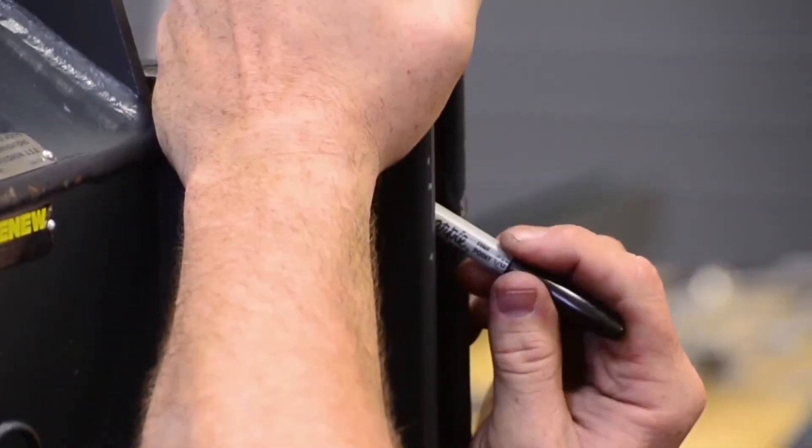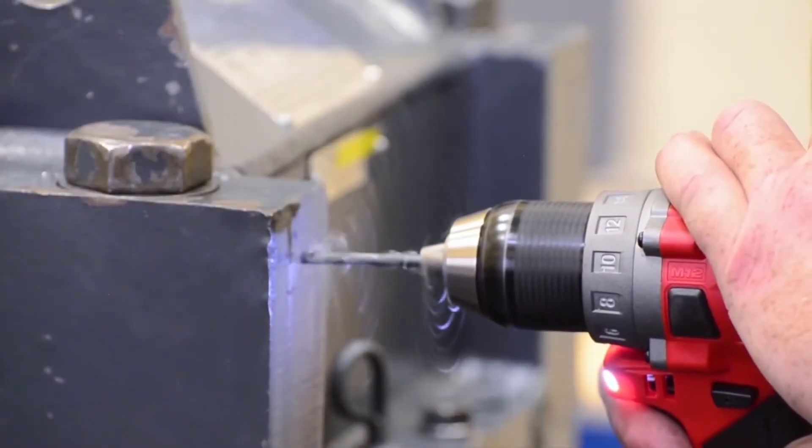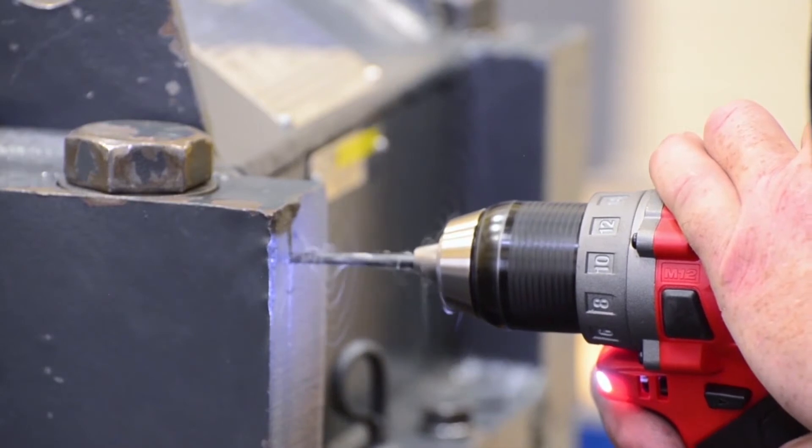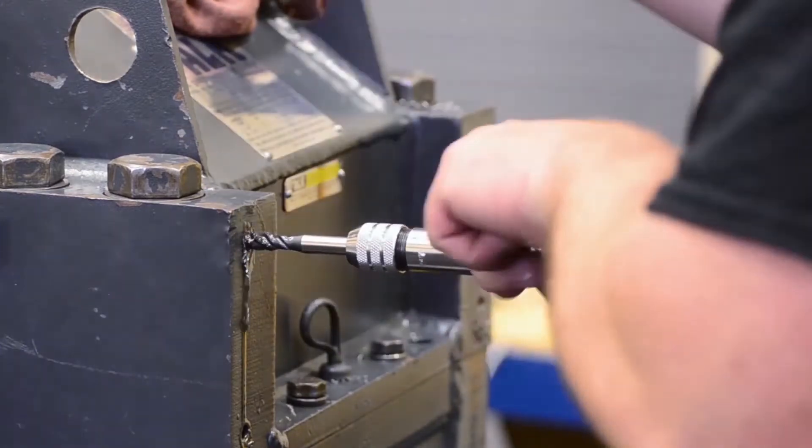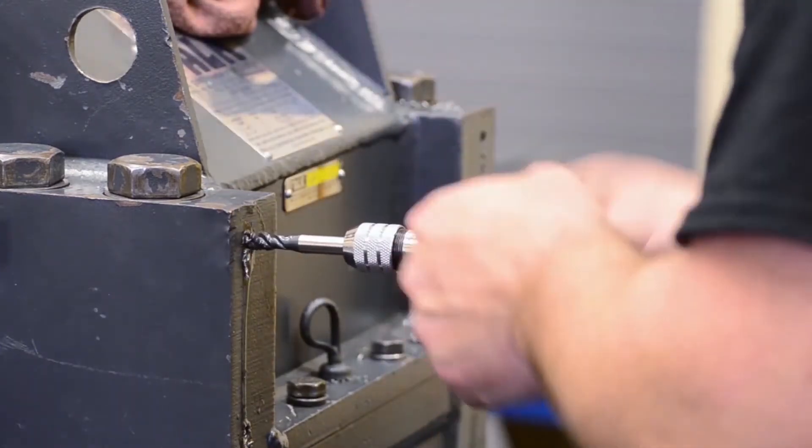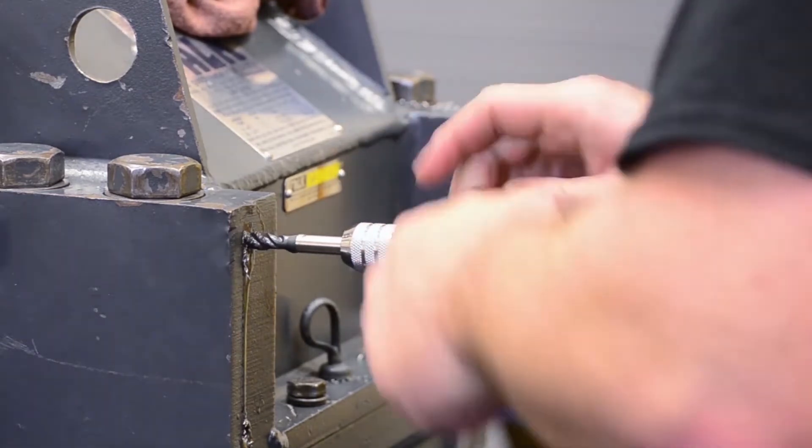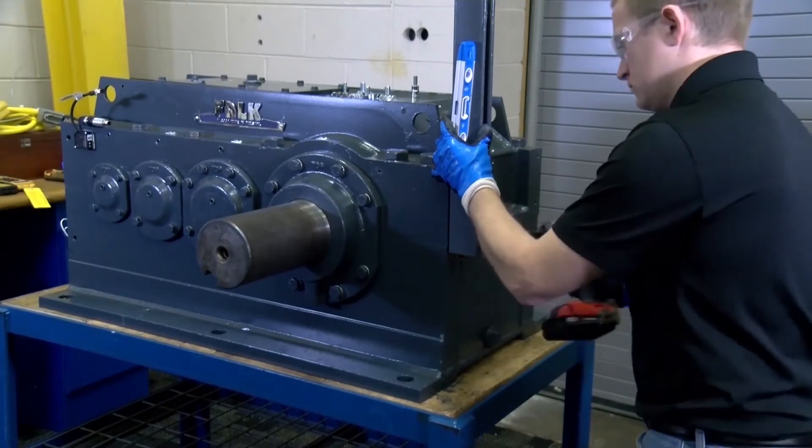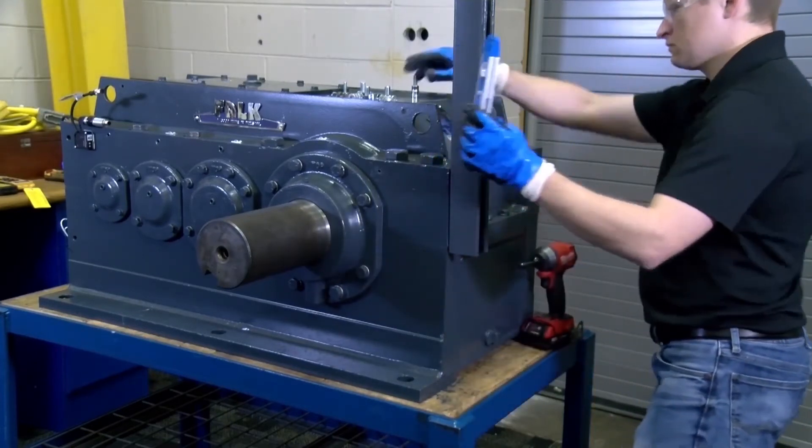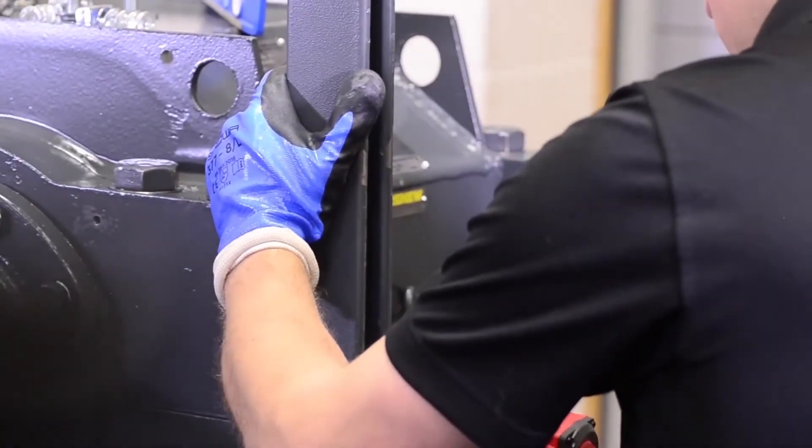Mark the hole locations on the drive and verify the positions align with the holes in the unistrut. Use an F-size drill bit and drill to a maximum depth of 0.45 inches. Using a 5-16-18 tap, thread the holes to a minimum depth of 0.35 inches. Cut the unistrut to length. Do not mount the edge device plate more than 18 inches above the gearbox. Secure the unistrut using 5-16 hardware.